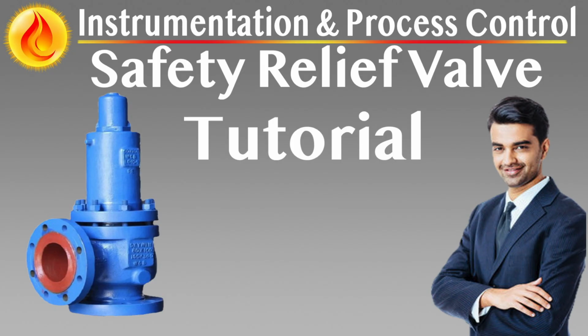Balance type relief valves. Pressure stable relief for variable and elevated back pressure conditions. Balanced relief valves are engineered to maintain accurate and repeatable performance even when significant or fluctuating back pressure exists in the discharge system. By incorporating a bellows or auxiliary balancing piston into the valve design, the effects of downstream pressure on the opening and closing forces are effectively neutralized. This ensures that the valve set pressure and lift characteristics remain stable, regardless of back pressure variations.